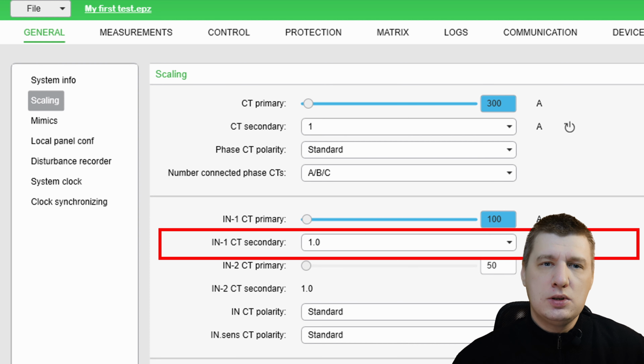Next, In1 CT secondary. We're looking at the primary current settings. We are zooming in on the secondary side, specifically for the In1 input. If you ever wonder why I often choose 1 amp over 5 amps for earth-fault protection, you should understand that 1 amp is more sensitive. The In1 CT secondary in your setup software is the rated output.